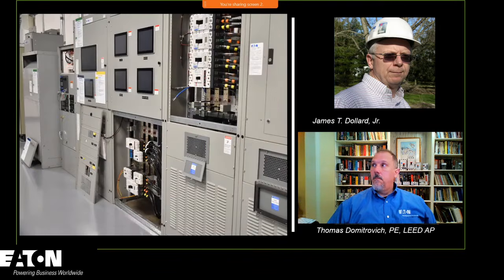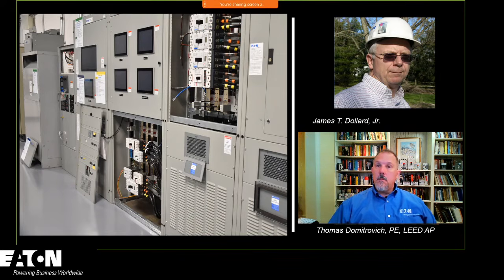What happens in many of those situations is that it's service equipment, and the engineer knows what the incident energy would be on the load side of that overcurrent protective device in the service equipment. So they can take a look at that, and it might be 2 calories. But since it's a 480 volt service, a Y connected secondary, since it's not self-extinguishing, the engineer says, well, if we get a fault on the load side that migrates to the line side, now what's my incident energy? And the engineer can't calculate that. The reason they can't is because it's all about current and time. They know what the current is, but there is no upstream overcurrent protective device that's going to open on the line side. So we get these crazy high numbers.